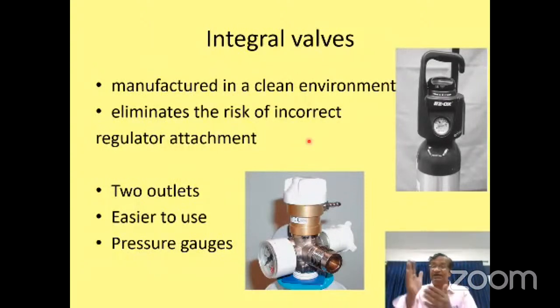Now, in the spindle valve itself, there is a pressure regulator. What is the advantage of this? You cannot exchange the pressure regulator between oxygen and nitrous, since it is an integral valve with the pressure regulator. There may sometimes be two outlets, one here and one here. So this is an integral valve, a valve with the pressure regulator and a gauge which tells how much the pressure is.